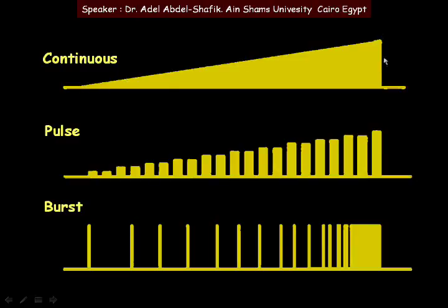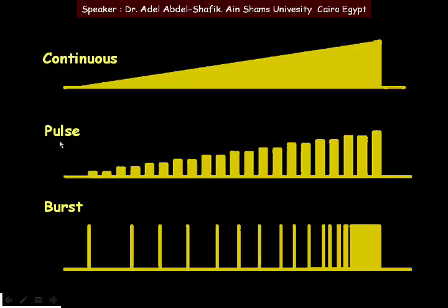To summarize: in continuous mode, phaco is on all the time. In pulse mode, there are pulses on and off. In burst mode, with surgeon control as you go deeper in position three, you increase power toward the preset maximum — for example, 70%. For burst mode specifically, pressing the pedal down shortens the interval between pulses until it reaches zero.